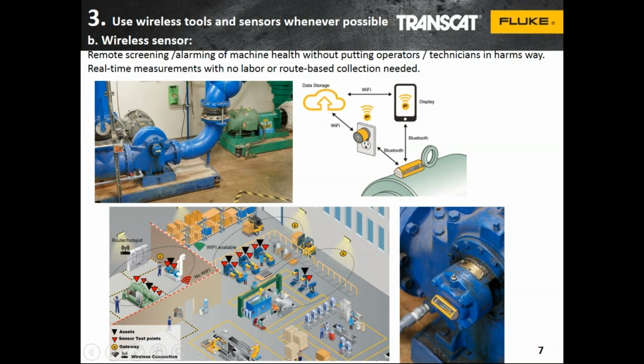And then on the lower left, you can see an example of a plant where your assets are the black triangles - these are your critical machines we want to monitor. The red square triangles are the bearings we would monitor on each one of these assets, and the G's are the gateways. That's where the vibration from these sensors goes to the gateways via Bluetooth and then up to the cloud, and now we get the data we need without having to have somebody walk around and collect data. So number one, it reduces the labor, but it also keeps people from having to go out into the space.